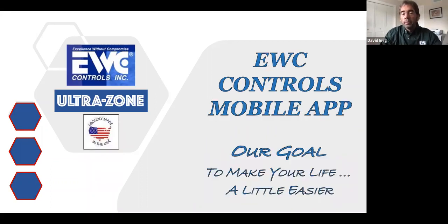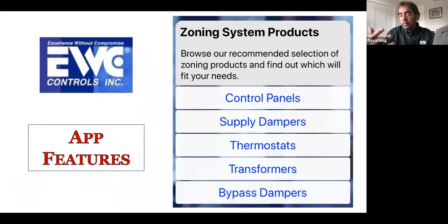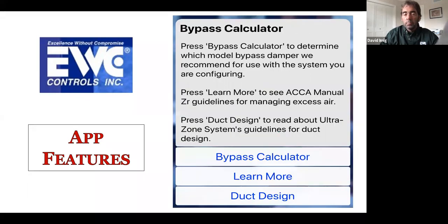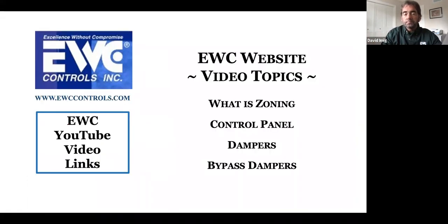Go to the App Store, search EWC Controls, and download our app. This app will give you features such as the ability to build your zone system. You feed it the information, we will select your control panel, supply dampers, thermostats, transformers, and bypass dampers. Another location, a bypass calculator. You feed us the CFM numbers that we ask, and we will select your bypass for you. There's also an area where you can download all of our tech bulletins or installation manuals of all of our product. Go to our website for some more assistance.